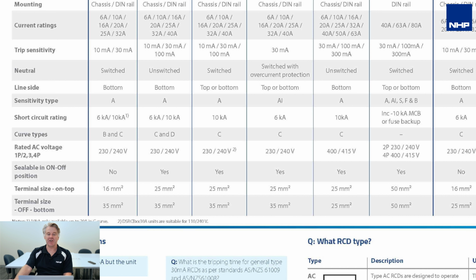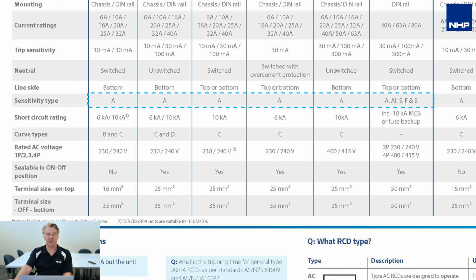The standards are changing on the type of RCDs that are required as a minimum. From the 30th of April 2023, AC device will no longer be accepted. So it's important to choose a type A RCD or greater. So here you can see the RCD types, type A, type AI, type S, type F and type B. So you need to ensure you choose the right one for the type of application. Always refer to the manufacturer's instruction of the appliance on what type of RCD is required, or make reference to AS3000 on guidance on the correct selection of RCD protection.